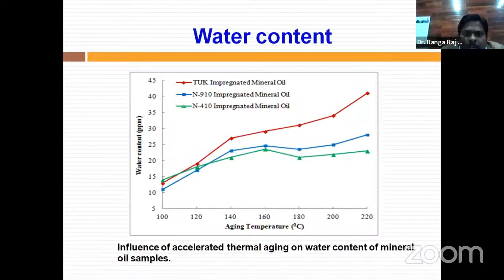Suppose you perform all 10 tests. Think the DGA test gives a good result with respect to dissolved gas analysis - all gases are in good or excellent condition. But maybe due to some electrical faults, the dielectric strength becomes weaker, so that test shows the condition as poor. And maybe there's a possibility of moisture, moderate level, while the furan content test shows good, excellent results. So different tests give different results with respect to their operating conditions - it's not that all tests give the same result.